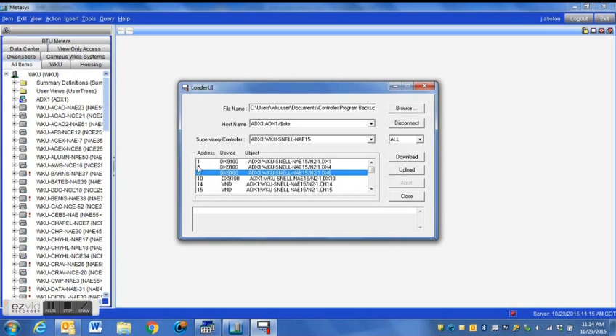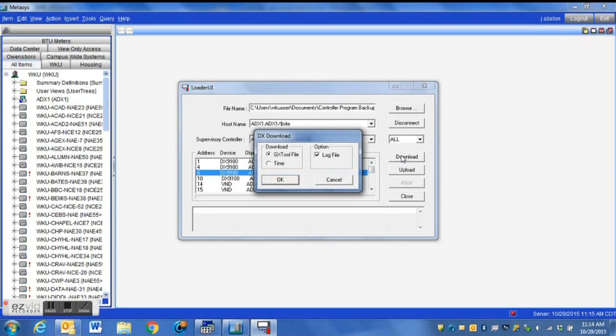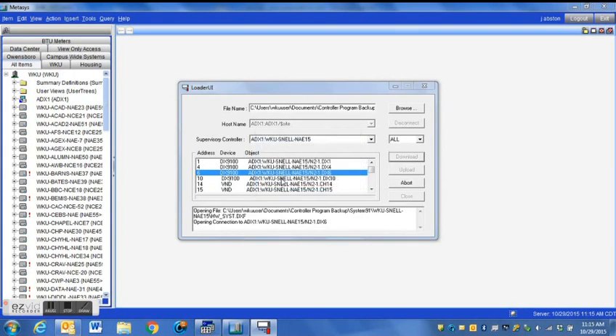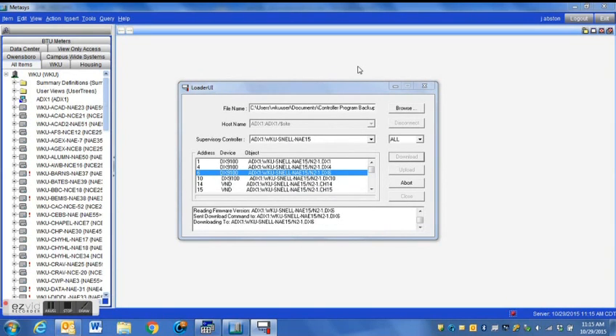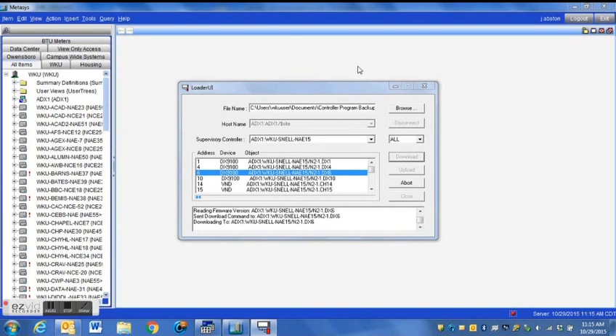Be careful, double check your address. You do not want to make a mistake here because if you load your program into an incorrect device, you can crash a system, you can crash whatever that controller was. So you want to make sure that you download the program into the correct device.